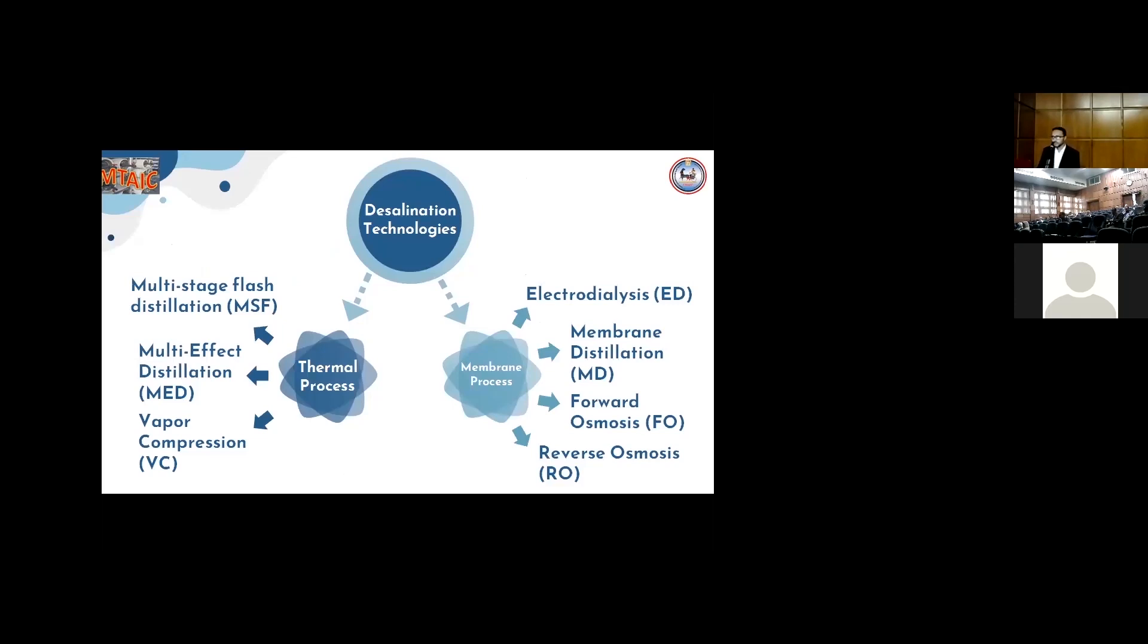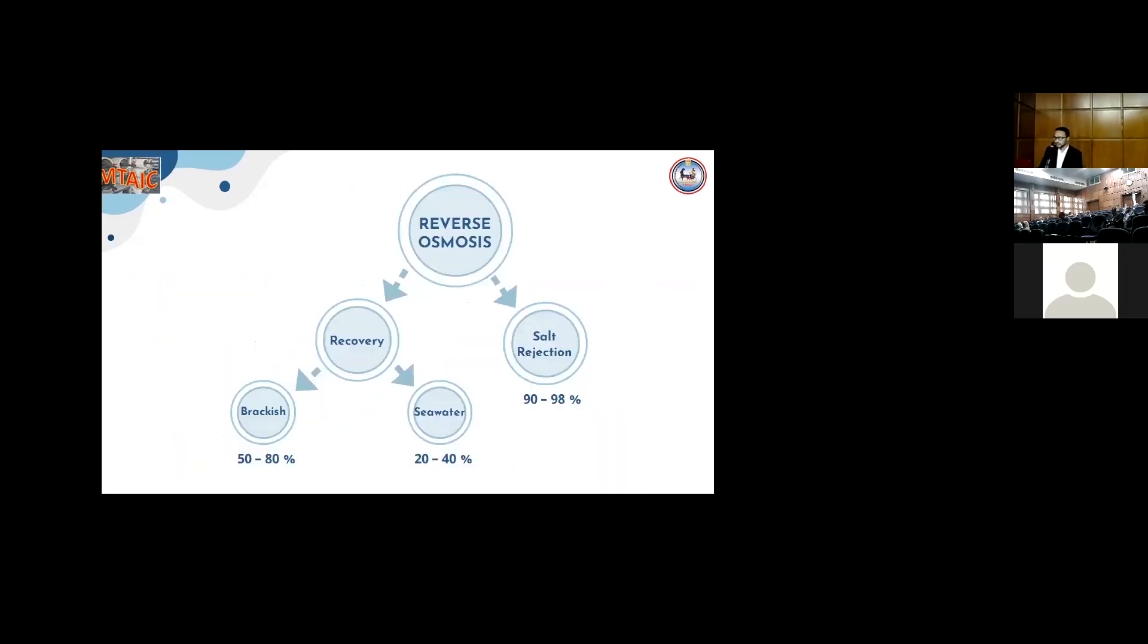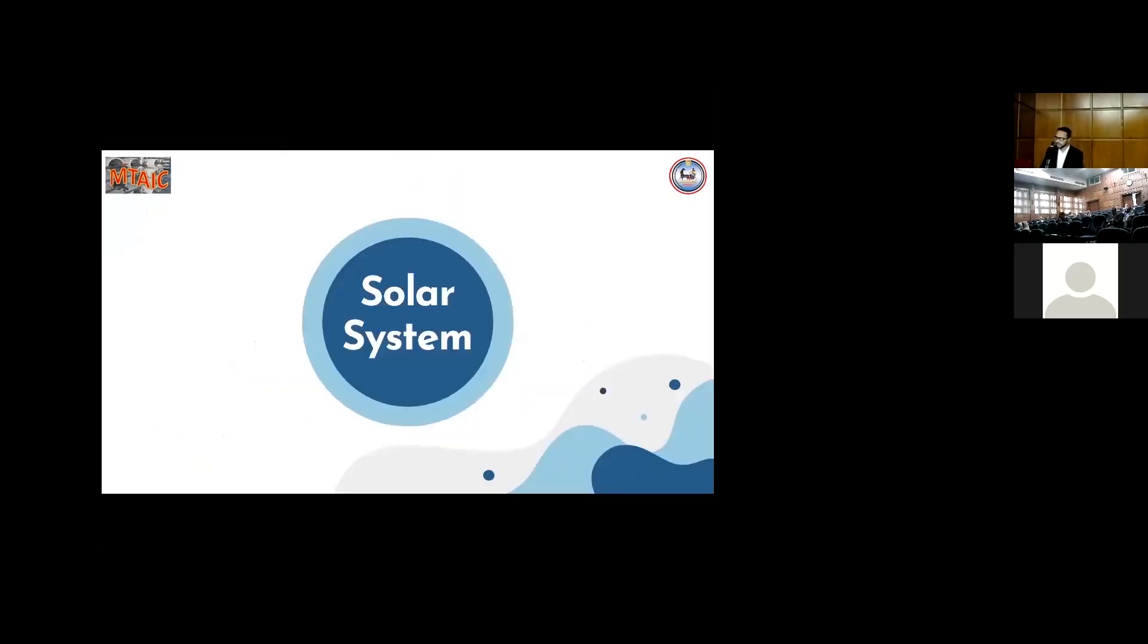The membrane process is preferred over the thermal process due to the higher operating costs and fixed costs. The RO has lower energy consumption, and overall is suitable for this freshwater desalination. The reverse osmosis has recovery from 50% to 80% in fresh water and from 20% to 40% in sea water, with salt rejection from 90% to 98%. However, the RO needs power that can be provided by solar system.